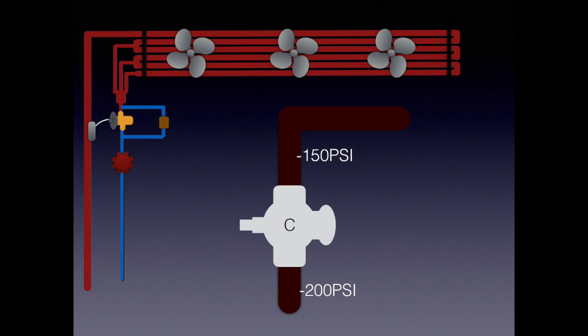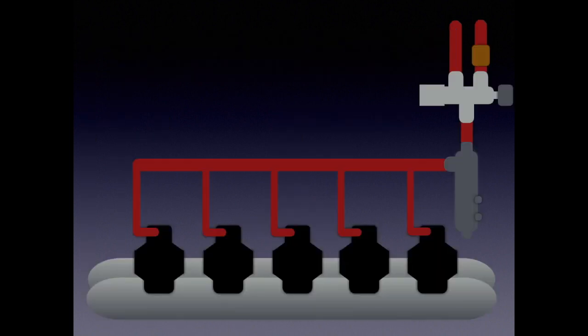The purpose of this is to allow that refrigerant to flow backwards. So that 200 pounds being pulled off of the receiver is greater than the 150 pounds on the liquid header. Higher pressure is going to travel to the lower pressure. So that was defrost there.